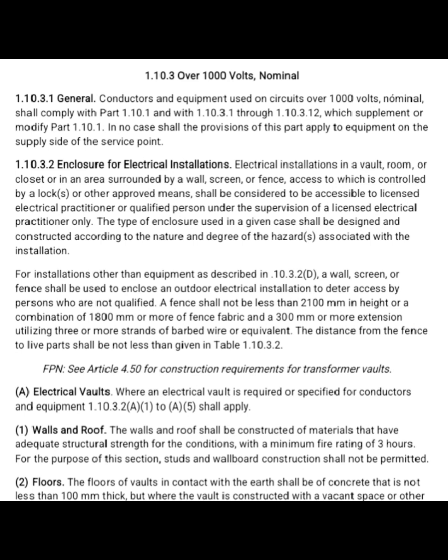1.10.3.2 Enclosure for electrical installation. Electrical installation in a vault, room or closet, or in an area surrounded by a wall, screen, or fence, access to which is controlled by locks or other approved means, shall be considered to be accessible to licensed electrical practitioners or qualified persons under the supervision of a licensed electrical practitioner only. The type of enclosure used in a given case shall be designed and constructed according to the nature and degree of the hazards associated with the installation.